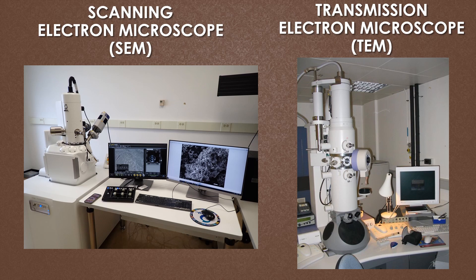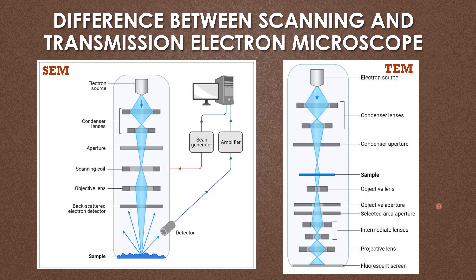Regarding the working principle, a majority of the parts are similar in both SEM and TEM, but the TEM contains some extra parts like selected area aperture, intermediate lenses, projective lenses, and fluorescent screen. Regarding the sample location, the sample is present at the end in the SEM, but in the TEM the sample is present in the middle, and parts like the objective lens are present above the sample.